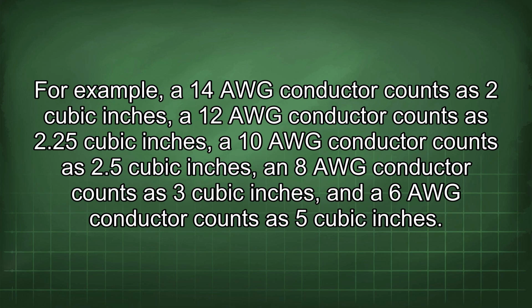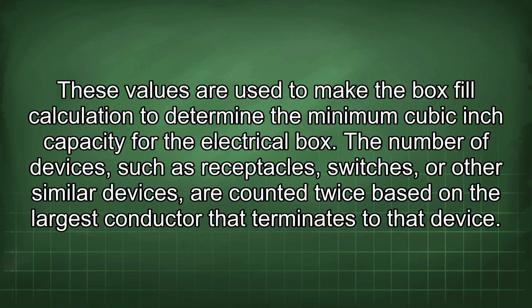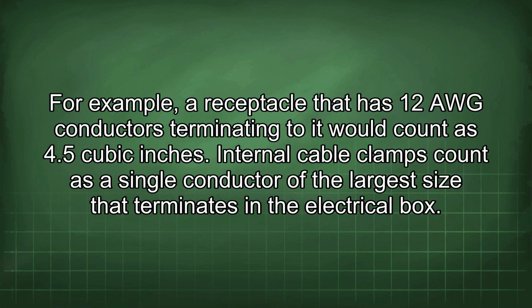For example, a 14 AWG conductor counts as 2 cubic inches, a 12 AWG conductor counts as 2.25 cubic inches, a 10 AWG conductor counts as 2.5 cubic inches, an 8 AWG conductor counts as 3 cubic inches, and a 6 AWG conductor counts as 5 cubic inches. These values are used to make the box fill calculation to determine the minimum cubic inch capacity for the electrical box. The number of devices, such as receptacles, switches, or other similar devices, are counted twice based on the largest conductor that terminates to that device. For example, a receptacle that has 12 AWG conductors terminating to it would count as 4.5 cubic inches.